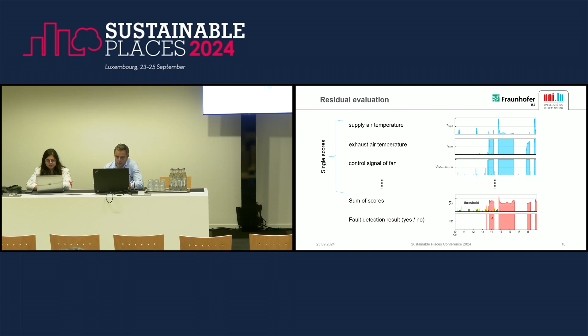We also made tests to assess the transferability of this approach, since it is one of the objectives - if you want to harvest all this potential across buildings, you need to transfer quickly from one building to another. We had 9 different air handling units of different sizes and topologies: one in Germany, in Berlin, with supply and exhaust air systems, a plate heat exchanger and heating coil; 3 here in Luxembourg with a heat recovery wheel, heating coil and adiabatic cooling; and another one, I don't know exactly the location, with the same topology as in Luxembourg.